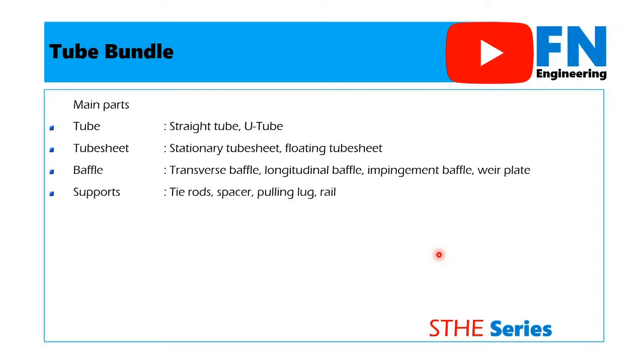For tube, there are two types: straight tube and U-tubes. Tubesheet also has two types, namely stationary tubesheet and floating tubesheet. The baffle has some types of parts including transverse baffle, longitudinal baffle, impingement baffle, and weir plate. Lastly, the supports of the tube bundle include tie rod, tube spacer, pulling lug, and rail.